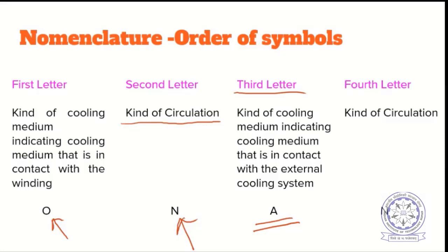It depends on the rating of the transformer. If you cool with water instead of air, naturally the cooling improves a lot, and the rating of the transformer increases. Or you can use more current to be handled by the transformer, or in other words, more power to be handled by the transformer.